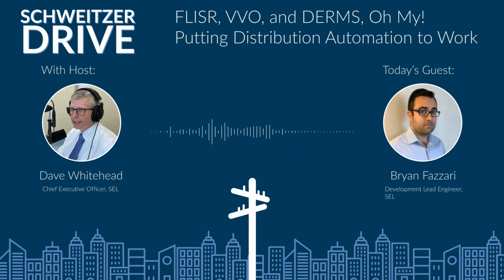Let's walk through how FLISR works. You've got breakers, reclosers, and switches sitting out on your distribution circuit, and a fault occurs—maybe a tractor hits a line, someone knocks down a pole, or a tree falls. There's a fault at that point, energy pouring into the ground, and the recloser closest to that fault is going to trip. If it's a permanent fault, it locks out, and any customers downline of that fault lose power—their power's out because a tree fell across the line.